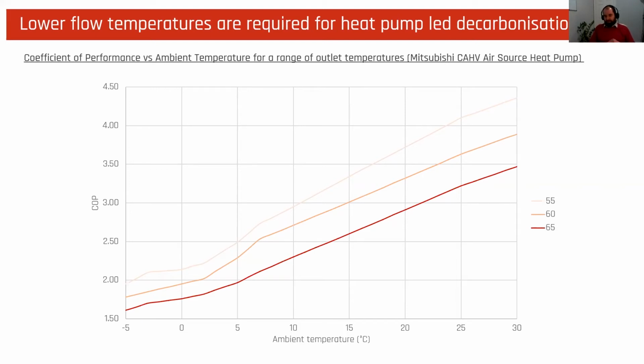And you can see in this graph, we've taken a very common heat pump on the market, looking at the efficiency. The COP on the left axis is effectively the efficiency of the operation. So if you have a COP of 3, you put in 1 unit of electricity, you get 3 units of heat out. For example, at an ambient temperature of 10 degrees, when it's 10 degrees outside, that same unit, if it was trying to generate heat at 65 degrees, would be operating below 2.5, something like 2.3. And if it only had to produce heat at 55 degrees, it would be up near a 3. So this obviously has a significant impact on the cost of heat to residents as well. The lower the COP, the more expensive the heat being generated by that technology is.